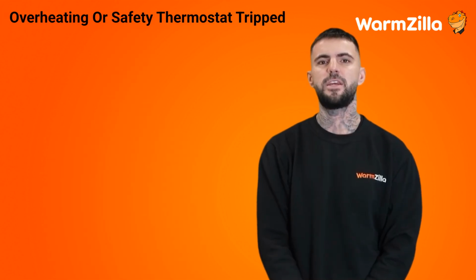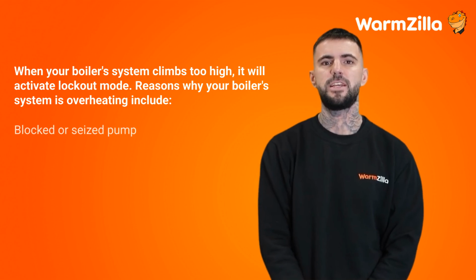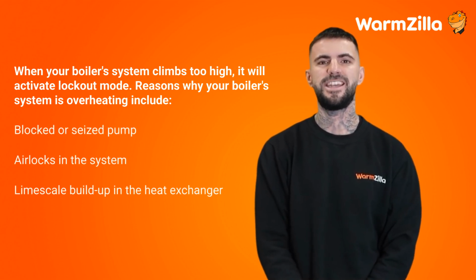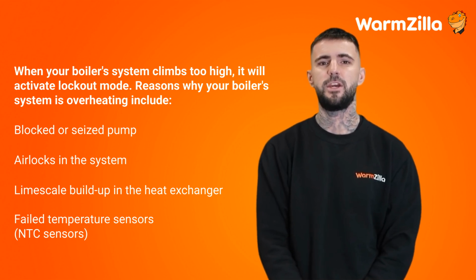Overheating or safety thermostat tripped. When your boiler system climbs too high, it will activate lockout mode. Reasons why your boiler's system is overheating include blocked or seized pump, airlocks in the system, limescale buildup in the heat exchanger, failed temperature sensors, NTC sensors. Resetting without addressing the root issue may cause repeated lockouts or permanent damage.